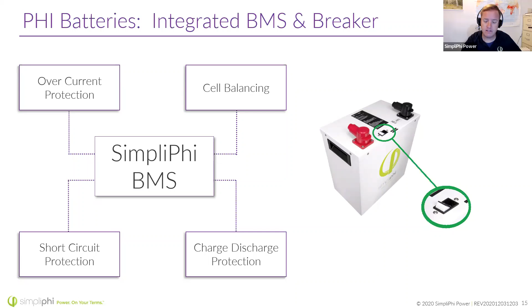We also have built-in breakers on all the batteries, which is a great advantage when it comes to installing the batteries. You can turn the battery off, move the battery in. You're not going to get any arcing. You're not going to have any risk of shorting out the battery. When everything's torqued, when everything is all nice and wired up, then you can go back and start turning on those breakers. It's also easy to do troubleshooting because you can isolate batteries in the bank, get your multimeter out and start testing things.